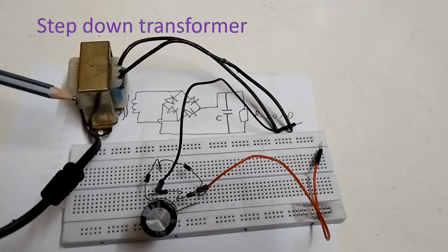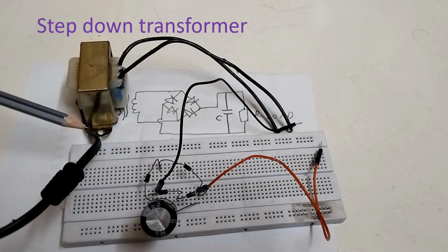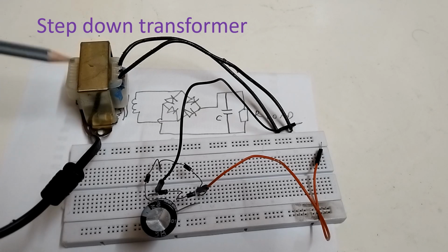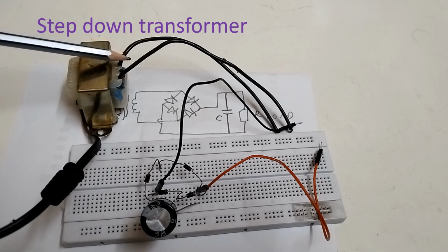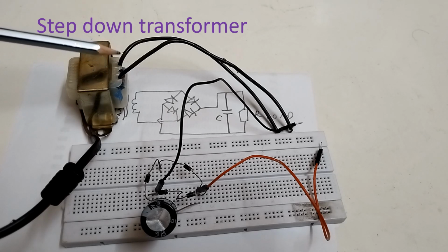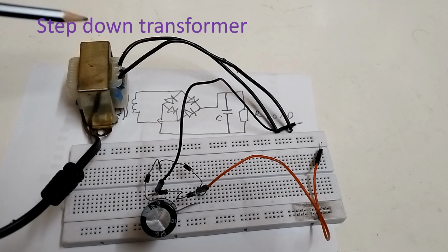So the number of turns will be much higher, and on the higher voltage side, as the current is lower and voltage is higher, you use thinner insulated copper wire. On the secondary side, as current will be more and voltage lower, you use thicker insulated copper wire. That is the usual pattern in step down transformers.